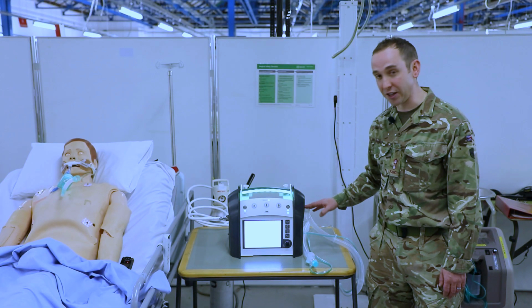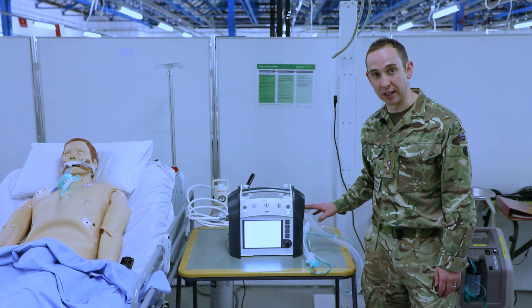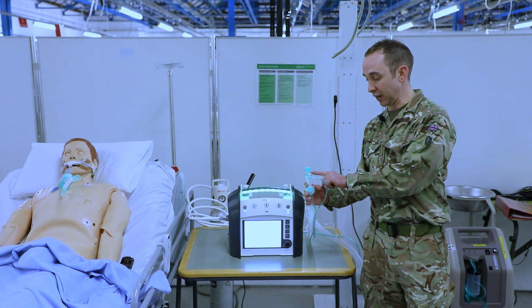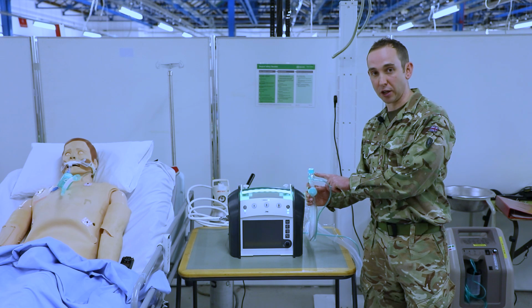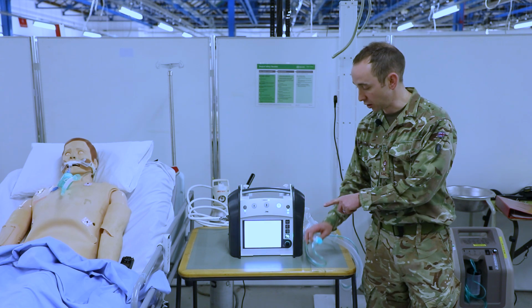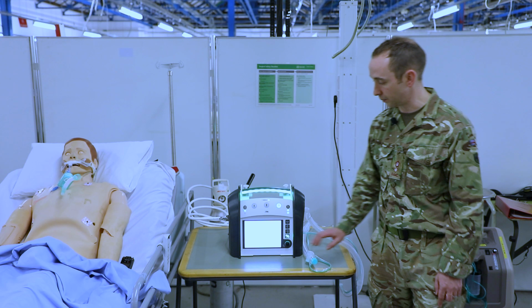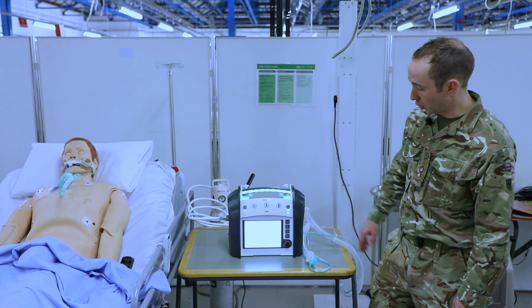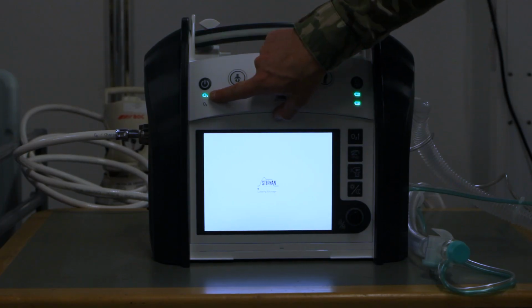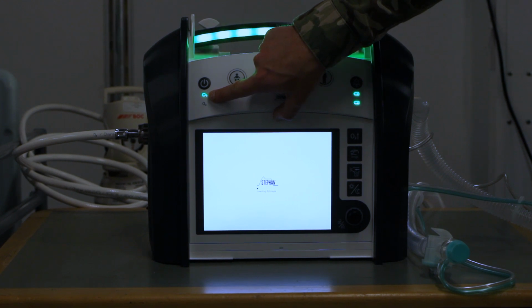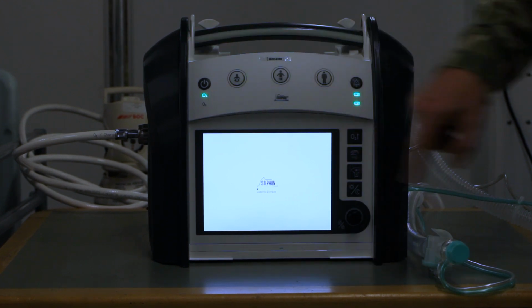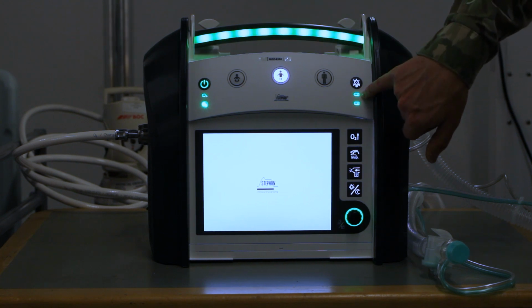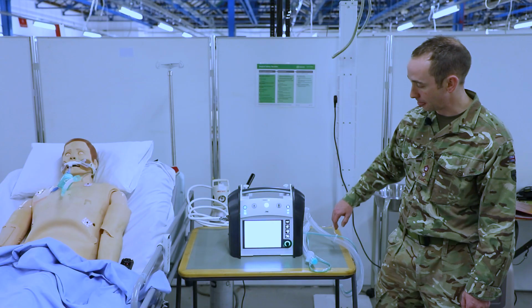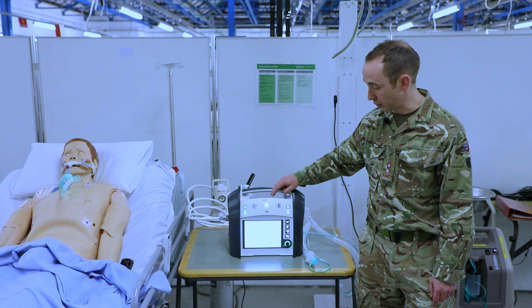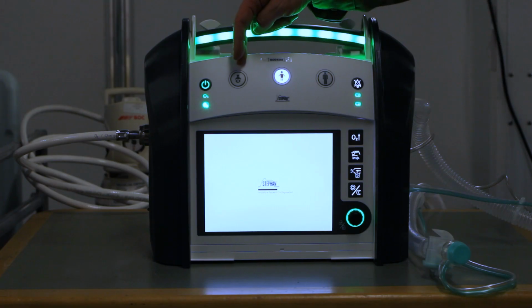Do note that I have a circuit connected, which is the only way you can get it through its self-test, and that we have capped off the end of the circuit itself, which must be done in all circumstances to ensure that it passes its self-test. As shown before, when we are connected to power, this will show up as a green light here to show we're connected to power, and because these batteries have more than 75%, they are currently showing as green on this side.